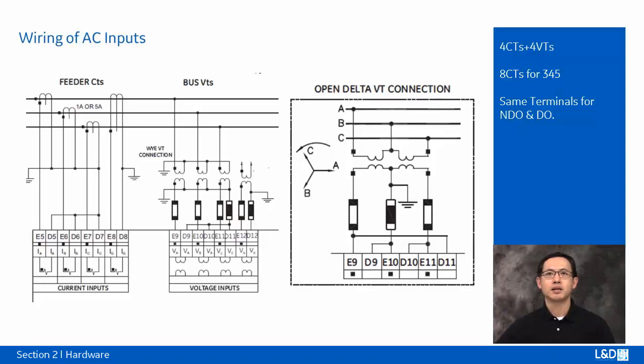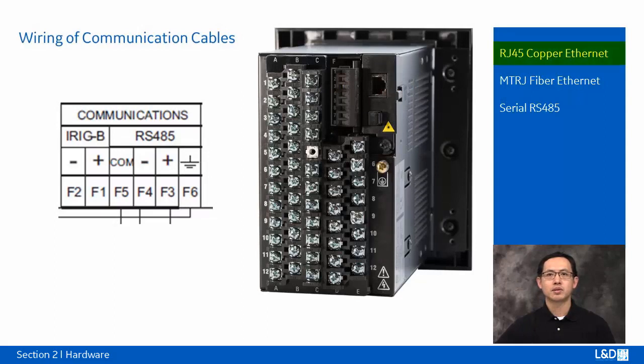3-phase inputs are designed as a bus voltage, and the connections most commonly used are Y and open delta. The single-phase input is designed as the auxiliary VT voltage. The auxiliary VT input channel can be connected for either phase-to-neutral voltage VAN, VBN, VCN, or for phase-to-phase voltage VAB, VBC, and VCA. For the Ethernet ports, there are RJ45 copper Ethernet or MTRJ fiber optical cable connection.